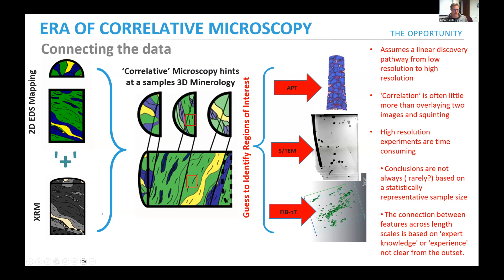We've entered what is called an era of correlated microscopy. The idea is that you take a sample, put it in an X-ray CT system, polish at least one surface, and take an energy dispersive spectroscopy map to get a chemical map. Overlaying these creates a correlative digital twin. From there you use expert knowledge to identify higher-resolution features to examine with SEM, FIB, STEM, or atom probe — always going from low-resolution millimeter-scale data down to potentially atomic resolution.